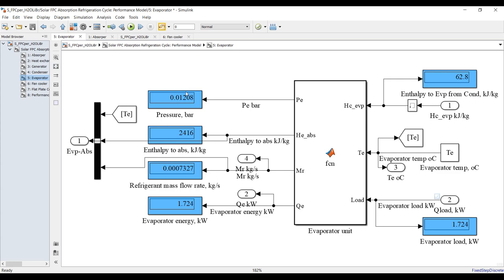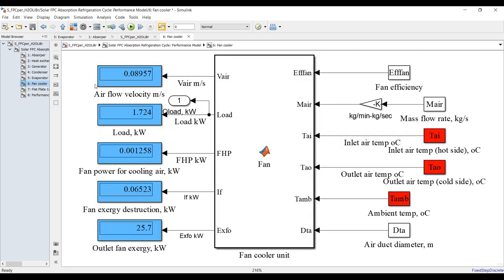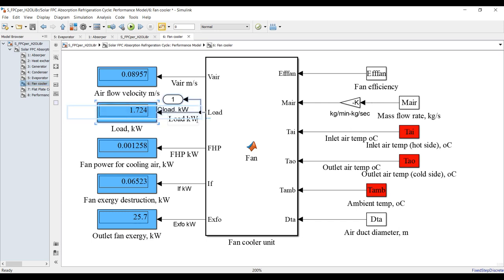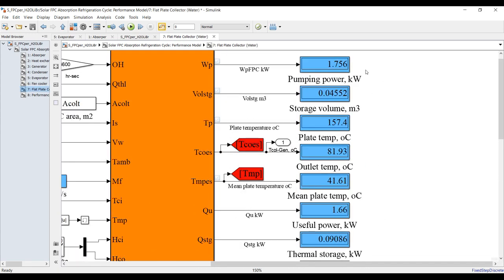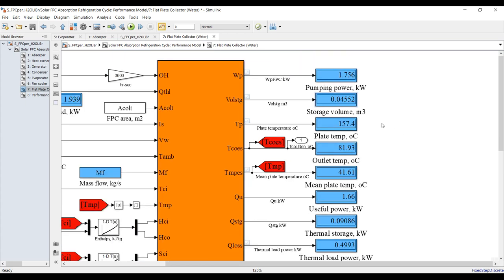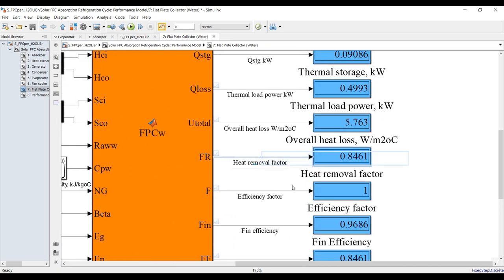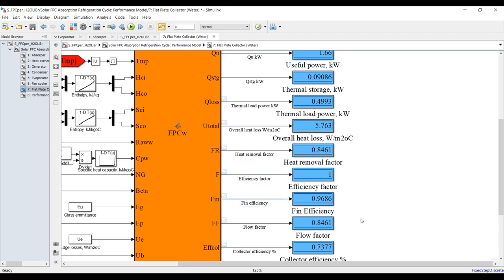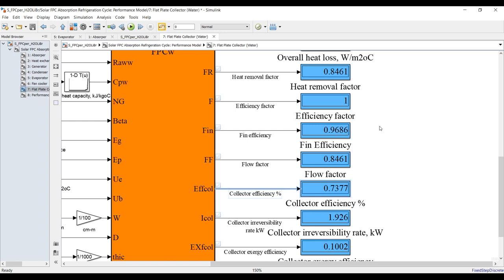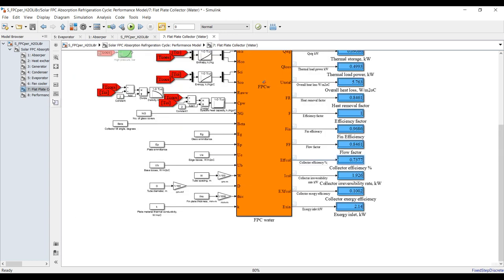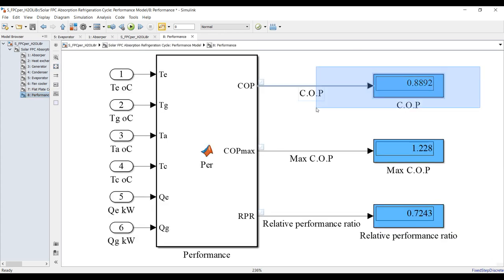For the evaporator and fan cooler, this is your cooling load. If you increase the mass flow rate, you will increase the load and the system will consume more thermal power. For the flat plate collector, outputs include pumping power, storage volume, plate temperature, outlet collector temperature, mean plate temperature, useful energy, storage energy, thermal losses, heat removal factor, fin efficiency, flow factor, and collector efficiency — currently 73 percent at this operating point.